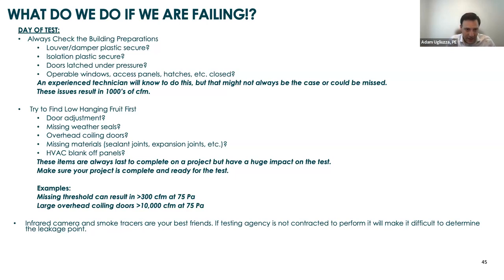If the testing agency doesn't have it, really question that. They should always have that equipment with them. Otherwise, you're going to need somebody else on site operating that, because that's your only method of really finding out what's going on if things are hidden or not apparent. So if you start getting into this test and you find the testing agency's not doing that and they're not being contracted to do that portion, don't be afraid to bring that along for your own sake, to figure out what's going on and how you can help the test actually pass.